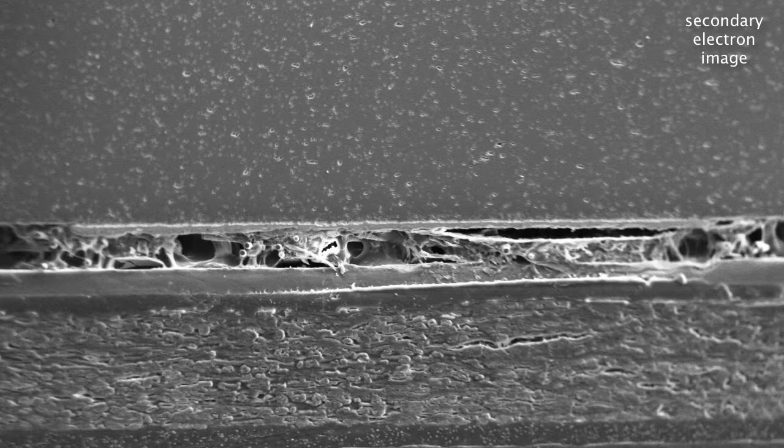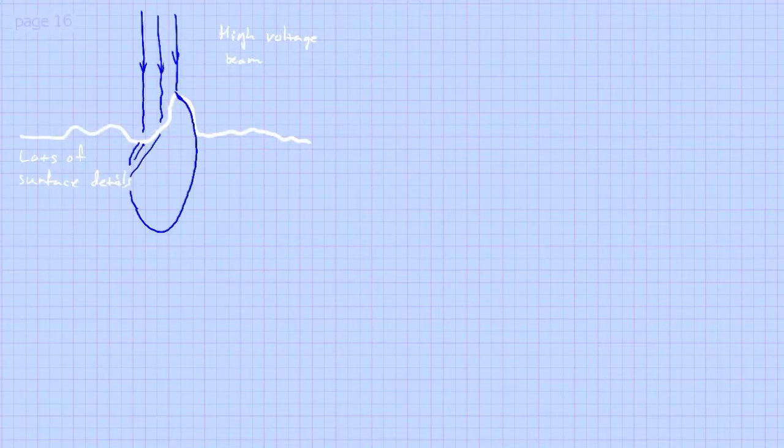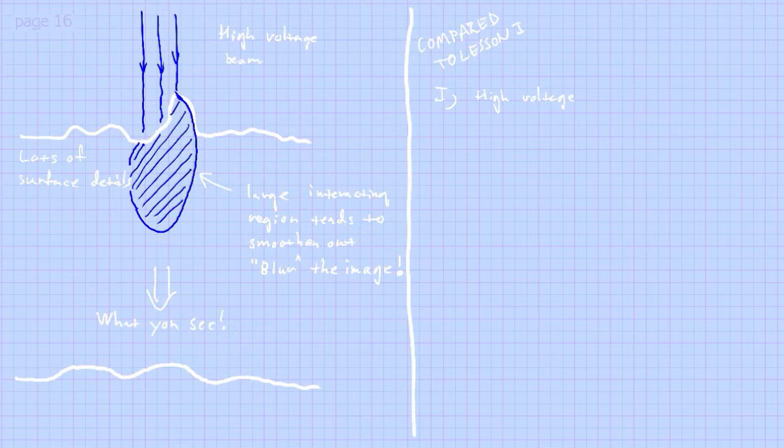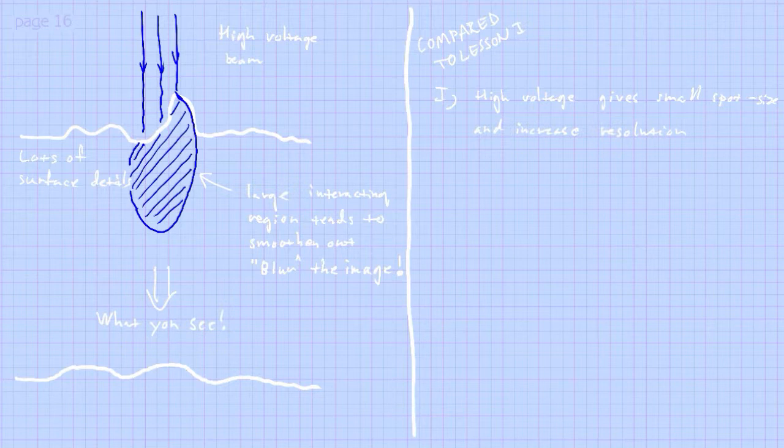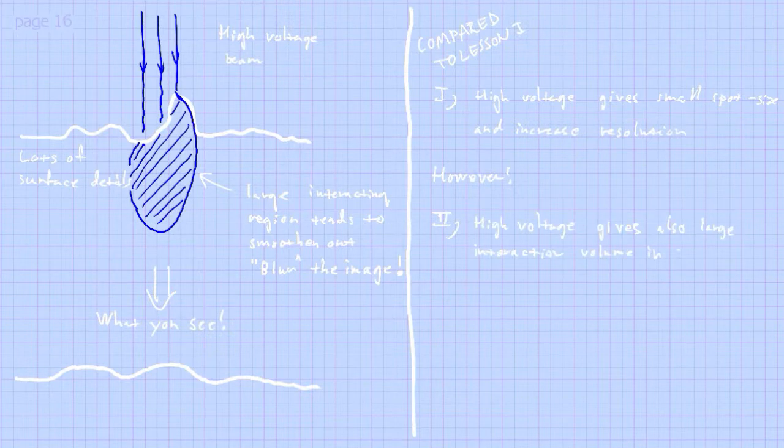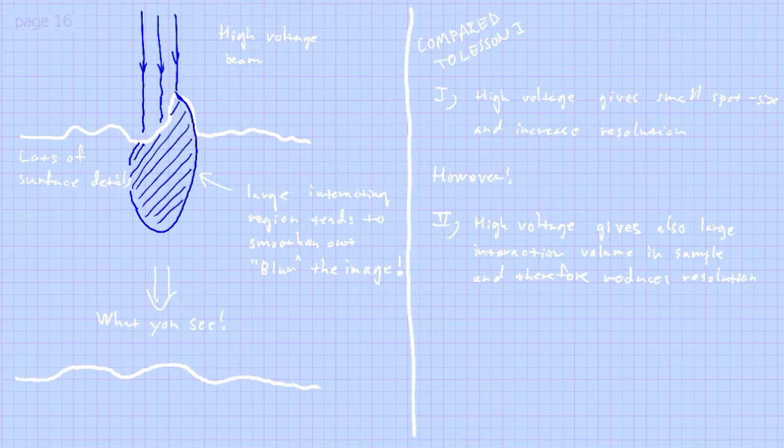But if you have a high accelerating voltage, then you will also have a big interacting volume in the sample, and that can reduce the resolution because you can't see the small details in the sample. That is sort of contradictory to what I said in the first lecture, because there we defined that the brightness was depending on the accelerating voltage. If you just increase the accelerating voltage, then you will optimize it and give it better resolution. So here you see the give and take situation. Theoretically high voltage is good from the gun viewpoint, but in the sample interaction viewpoint, that might actually be bad. So this is a give and take situation, so you need to optimize this depending on the sample.